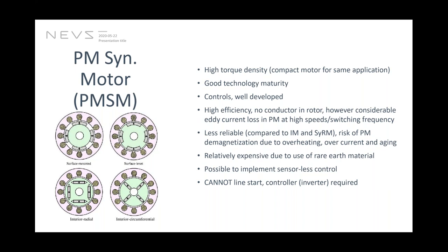Possibility to implement sensorless control, and yes, it is relatively easy compared to induction machine and synchronous reluctance machine to implement the sensorless control in the permanent magnet machine actually. Another thing is this, it cannot line start on its own. It needs an inverter or a specially designed rotor for it to be a line start motor. So basically you almost always will require the controller to make it run. So that's why older generation HVAC unit or industrial process probably would never have used this permanent magnet.